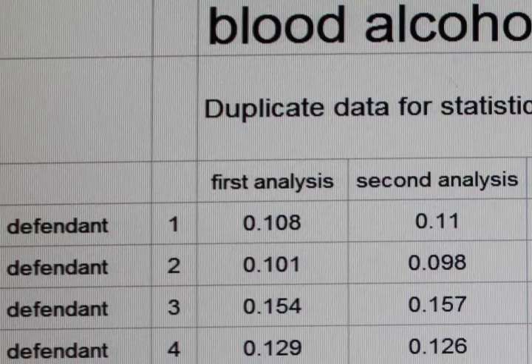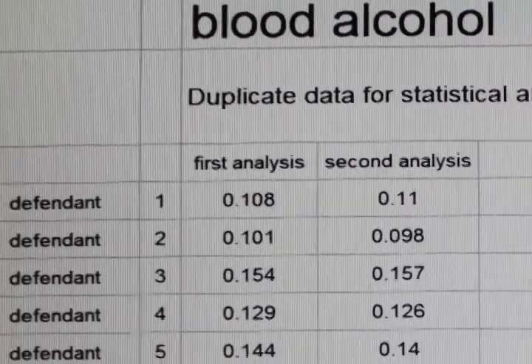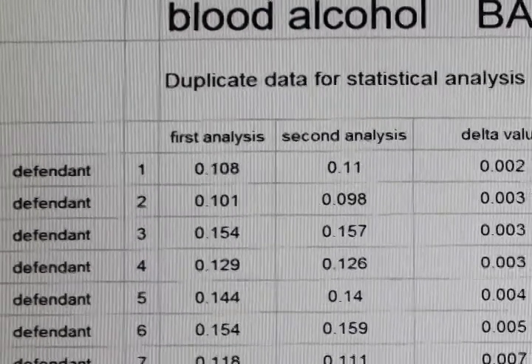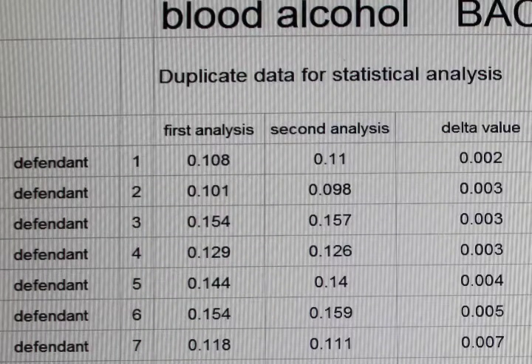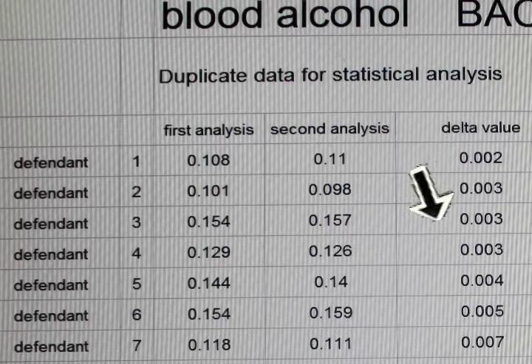How do we look at the errors? The standard approach is to run controls, look at the spread of the controls, and that will tell you what the errors are. But you can see the errors right in the duplicates. So let's add another column and call that column the delta, which would be the absolute difference between the first and the second one.